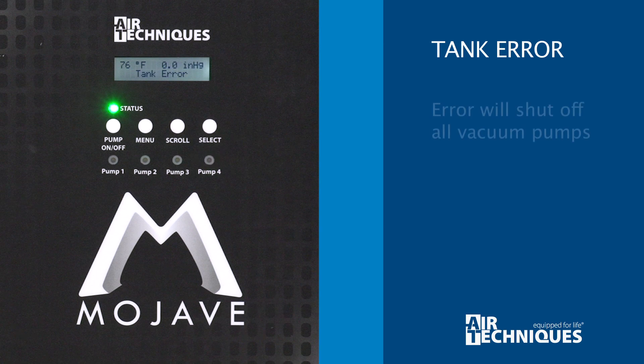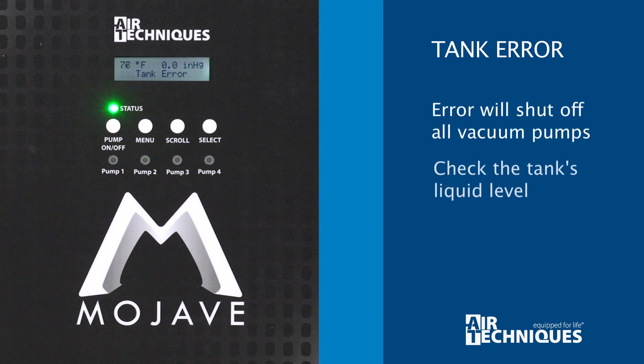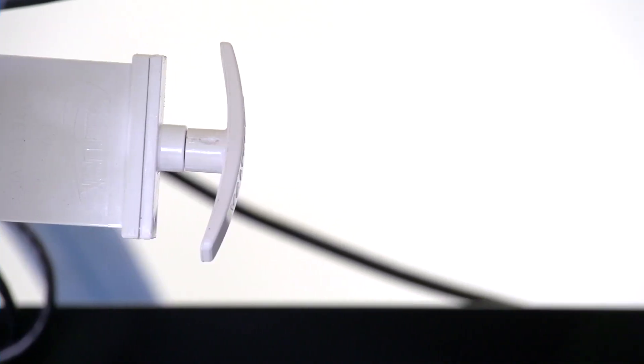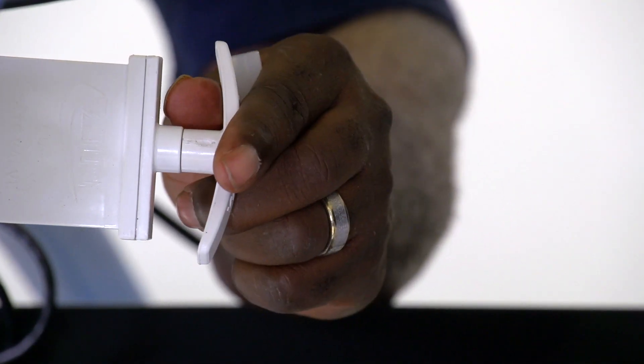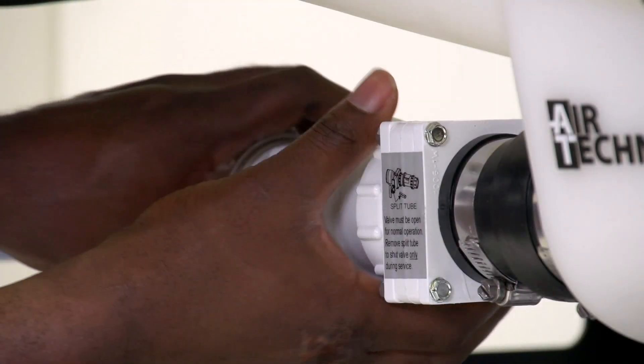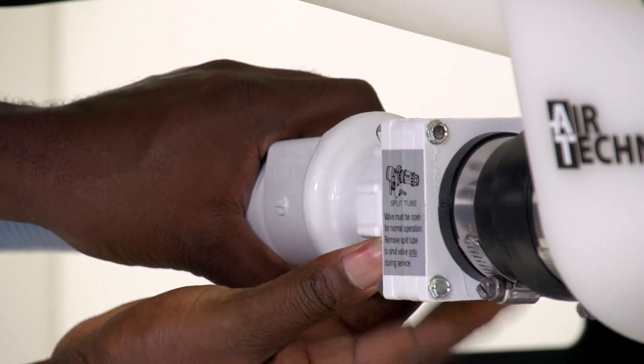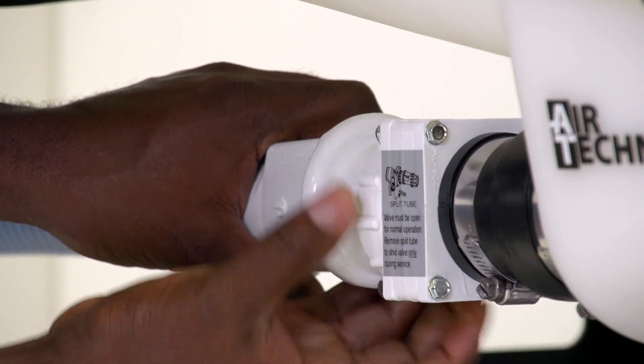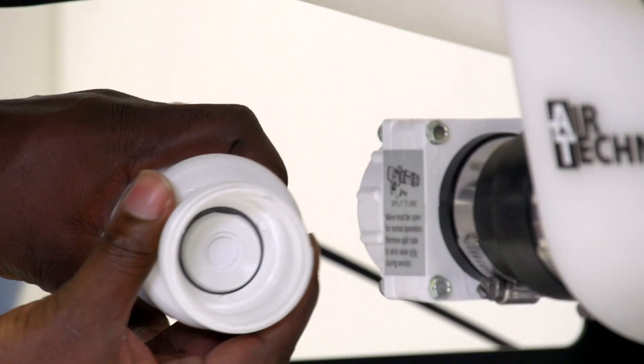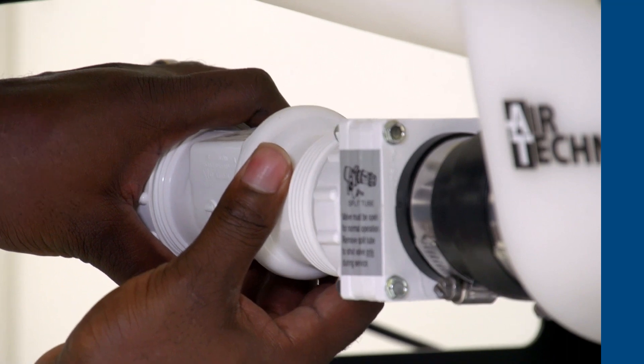The tank error shuts off all vacuum pumps. Check the liquid level in the tank. If it is high, ensure that the gate valve is open and the tank drain check valve is not clogged. Open the valve and/or fix the clog and allow one minute for the tank to drain, and the pump should turn back on automatically.